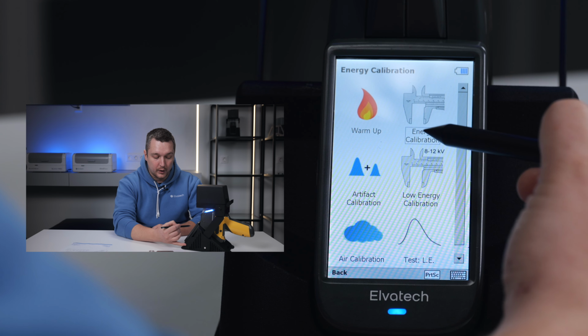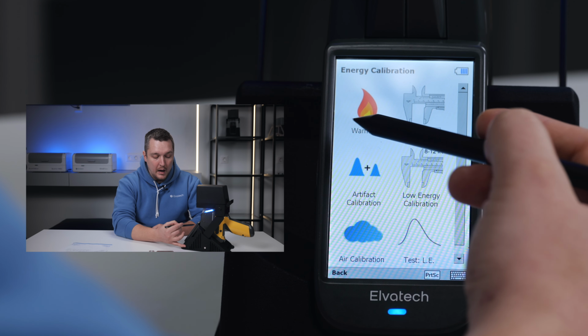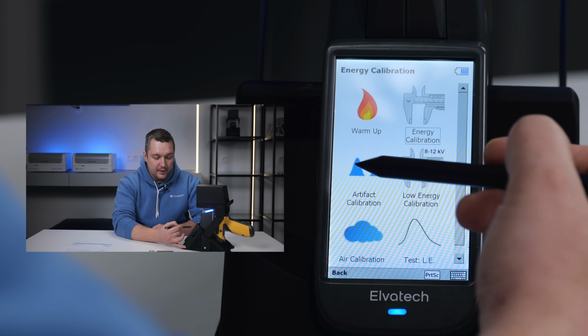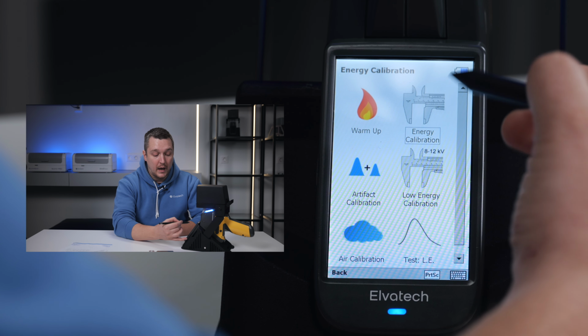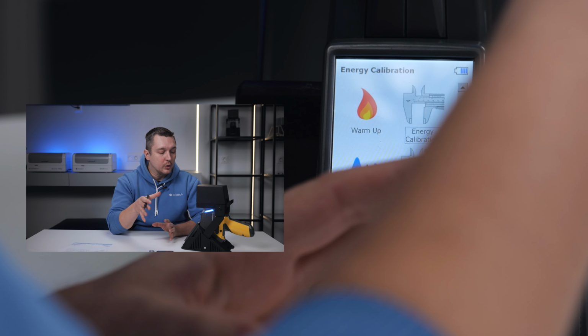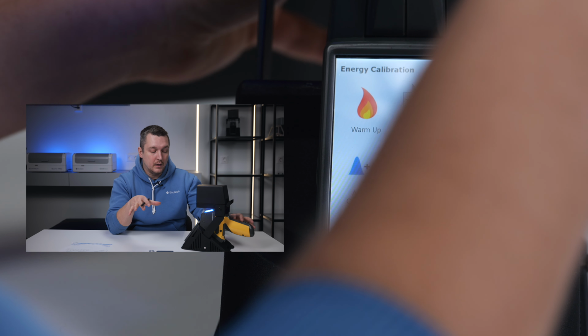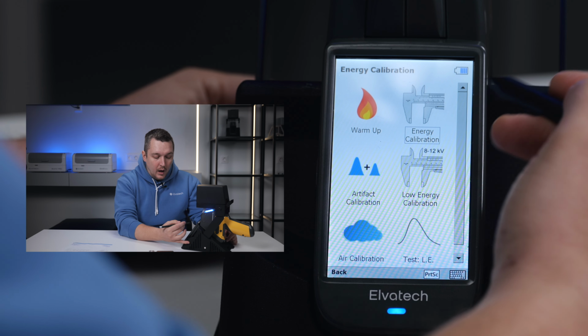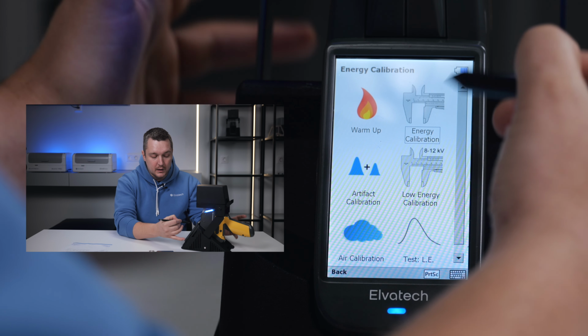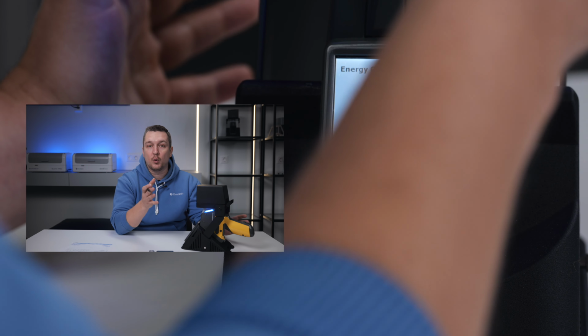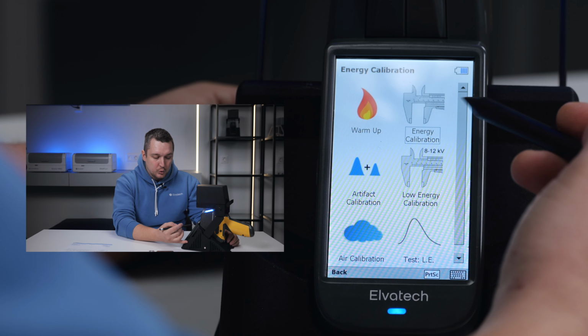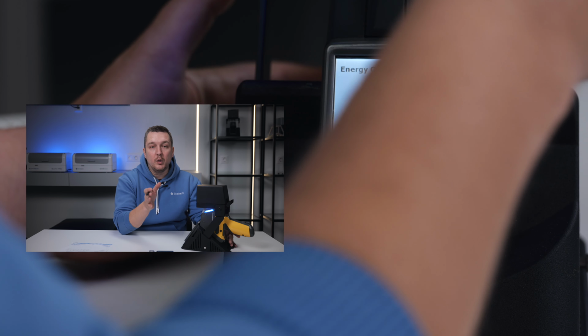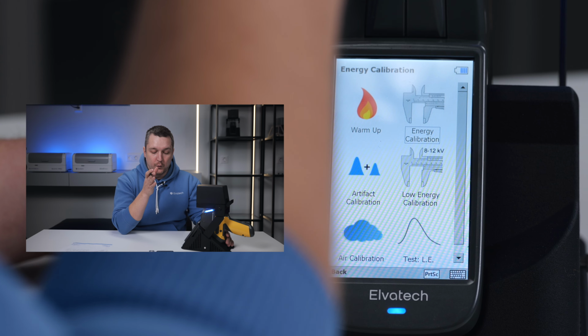So just click on the folder energy calibration, and here you see the warm-up, energy calibration, low energy calibration, artifact calibration, and so on. We are interested particularly in energy calibration and low energy calibration. If you have the model of the ProSpector 3 without light elements, with the blue body, you will have only the energy calibration. It's for the heavy elements. But if you have the model with the light elements, you will see also the low energy calibration. It's for the calibration for light elements. To perform the calibration, first we perform the energy calibration for the heavy elements, and after that we will perform it for the light elements.